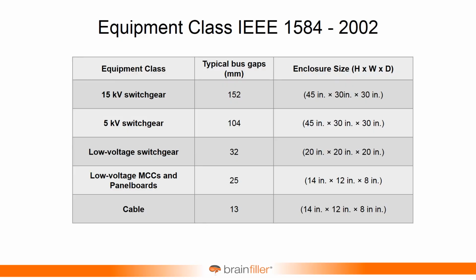From the 2002 edition of IEEE 1584, we just had a handful of what we called classes of equipment. And those of you that use software, this is one of the functions that you set up in the software. It usually says equipment type. It's really class, but it'll say equipment type, maybe it says class. And you select, is it medium voltage? Is it low voltage? Usually like distribution equipment, panels and switchboards. Or is it low voltage power equipment, like low voltage switchgear? And so these were basically the categories that you had, the equipment class.